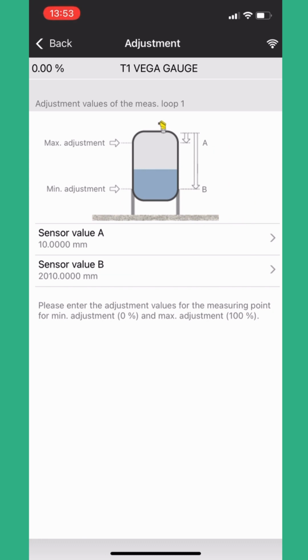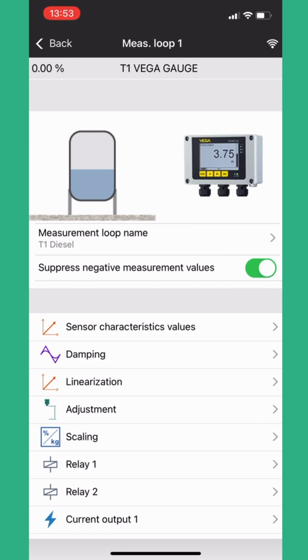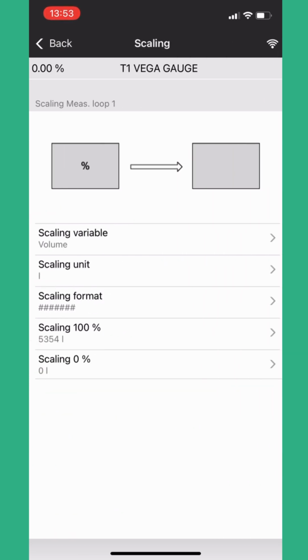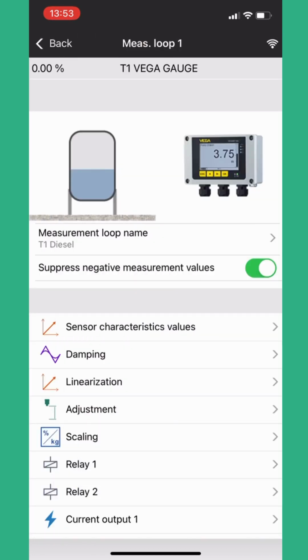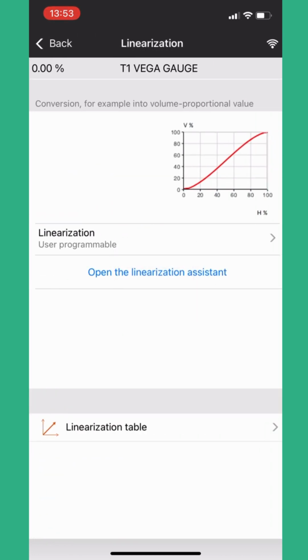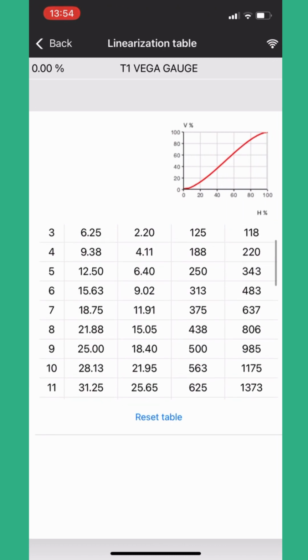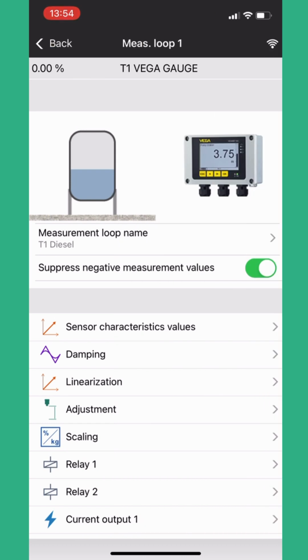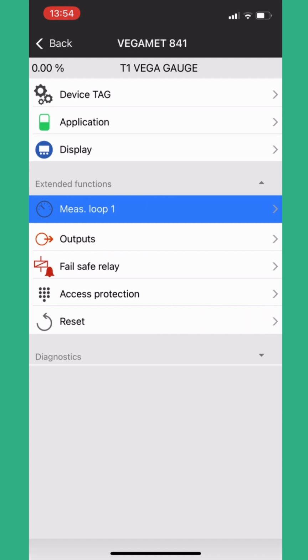We can make adjustments to the sensor settings that we inputted originally using the quick wizard. We can adjust the scaling, change the volume, change how it displays, and we can adjust the linearization. We can change the tank chart. We can tell it that it's no longer a horizontal cylinder, but a rectangular. Lots of options within that setting.